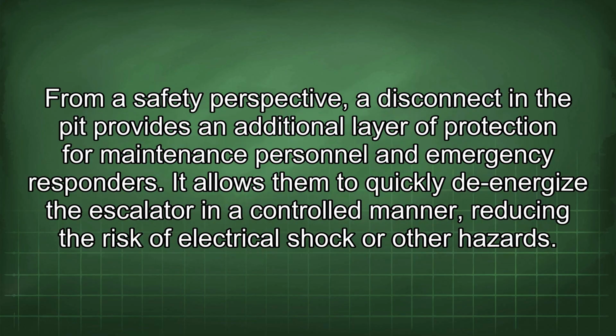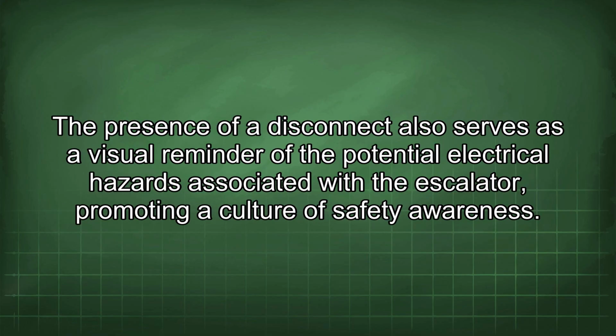From a safety perspective, a disconnect in the pit provides an additional layer of protection for maintenance personnel and emergency responders. It allows them to quickly de-energize the escalator in a controlled manner, reducing the risk of electrical shock or other hazards. The presence of a disconnect also serves as a visual reminder of the potential electrical hazards associated with the escalator, promoting a culture of safety awareness.